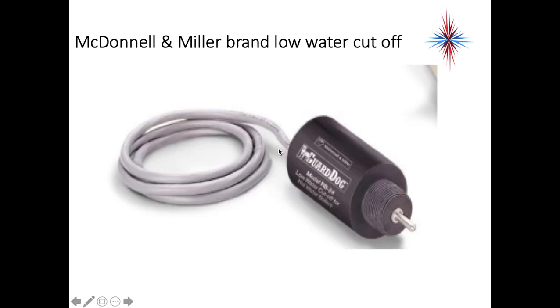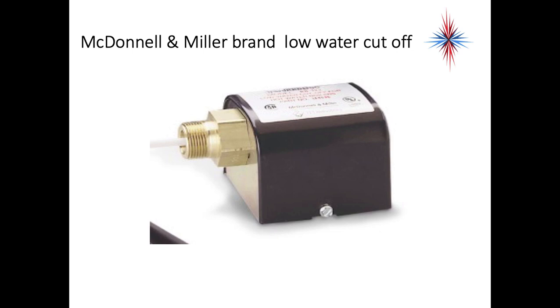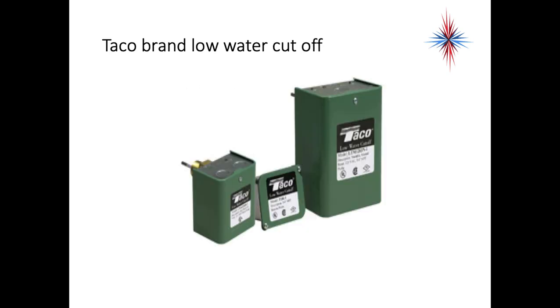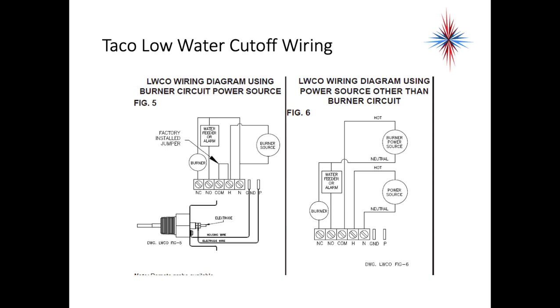This is an example of a low water cutoff that screws into a fitting on the boiler. This sensor uses an electrical current between the outside and the inside to sense that there's water in the system. Here's another one that uses water pressure. You can also see a wire diagram — it comes off the transformer furnished with the boiler, with a red, white, and a yellow wire that interrupts the power to the Aquastat. The whole purpose of this is that it interrupts power to the burner and will not allow the burner to fire if there's no water or too little water in the system.